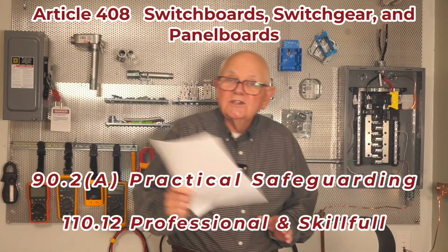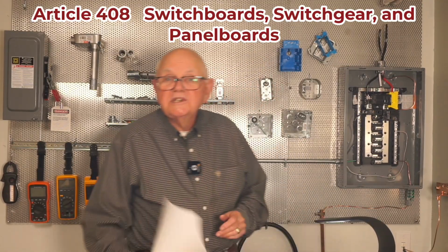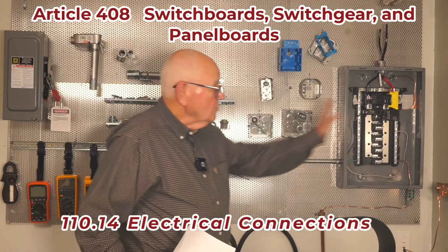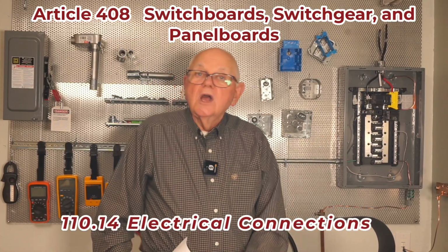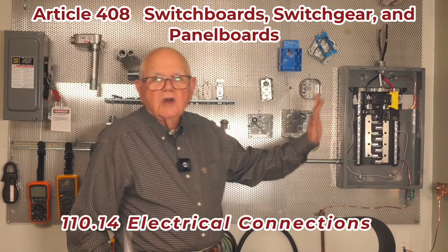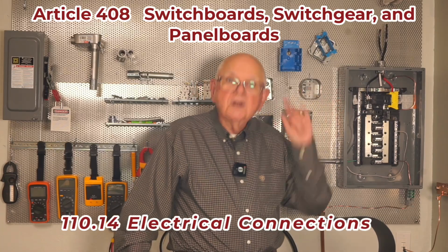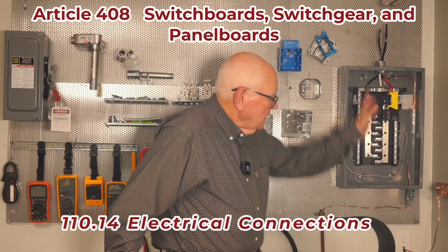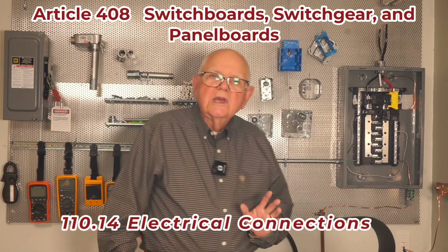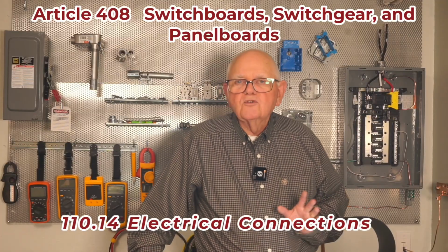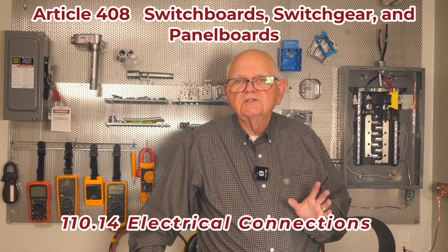So if I don't do things, for instance, 110.14 says I have to torque my terminal connections. All of those requirements don't say, well, I don't know what they should be. No, look on the breakers, they'll tell you. Look in the labeling inside the panel board. It will tell you what the torque requirements are for the different termination screws.